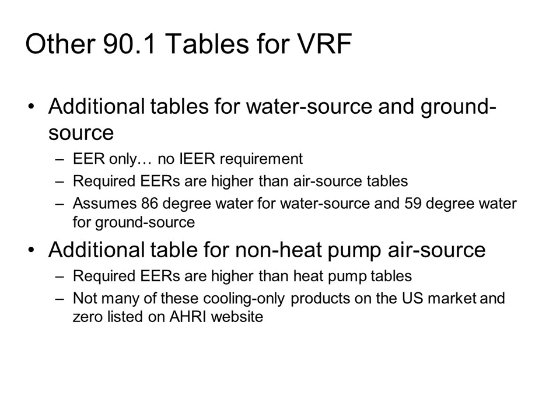There is one other table that you will find in ASHRAE 90.1, and it is completely useless, but many people I've noticed are going to that table and thinking that's the one they've got to follow because it's the first one on the 3 pages. That table, when you read the heading of it, is actually for cooling-only systems. Nobody that makes VRF is putting cooling-only systems in the U.S. market, so it's completely irrelevant, and there's none of them on the AHRI directory website, so just ignore that first table. It doesn't do anything at all. Skip the first table and go to the heat pump system, because in the U.S., all VRF systems are heat pumps.